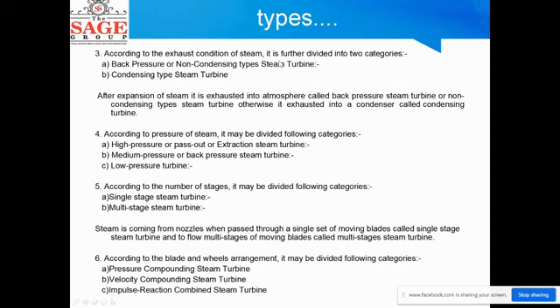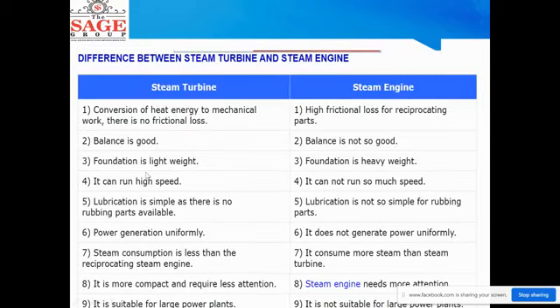According to the exhaust condition of steam, turbines are divided into two categories: back pressure (non-condensing) steam turbine and condensing type steam turbine. After expansion, if steam is exhausted into the atmosphere, it is called a back pressure steam turbine. According to pressure, turbines may be divided into high pressure, pass-out, medium pressure, and low pressure categories. According to the number of stages, they are divided into single stage and multi-stage. When steam from a nozzle passes through a single set of moving blades, it is called a single stage steam turbine. According to blade and wheel arrangement, they are divided into pressure compounding, velocity compounding, and impulse compounding.